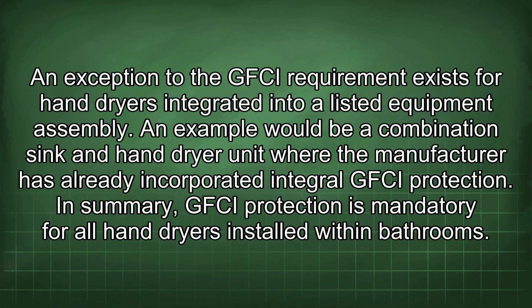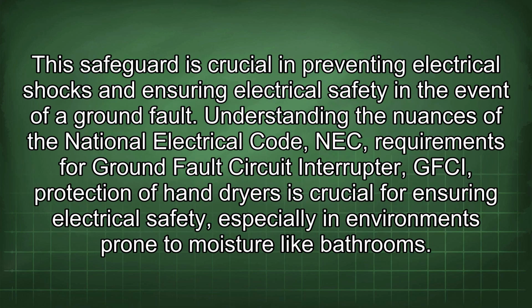An exception to the GFCI requirement exists for hand dryers integrated into a listed equipment assembly. An example would be a combination sink and hand dryer unit where the manufacturer has already incorporated integral GFCI protection. In summary, GFCI protection is mandatory for all hand dryers installed within bathrooms. This safeguard is crucial in preventing electrical shocks and ensuring electrical safety in the event of a ground fault.